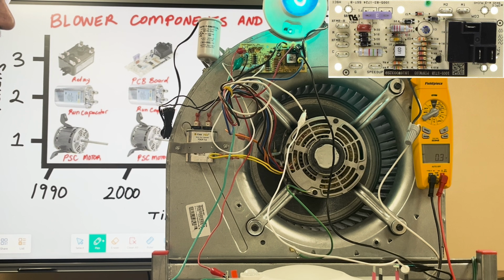Now, this does take a little bit of experience from a technician, so it's always best to make sure that somebody experienced is taking this project on. But don't take out that 3 amp fuse and replace it with a 7.5, a 10, a 15, a 20 just because it fits in there. If it's a 3 amp fuse and it blows, put another one back in there. If the fuse keeps blowing, the last thing you want to do is bypass it, because then you're going to blow your transformer. And then that's not good. You're just creating more work. It's going to be a bigger headache.